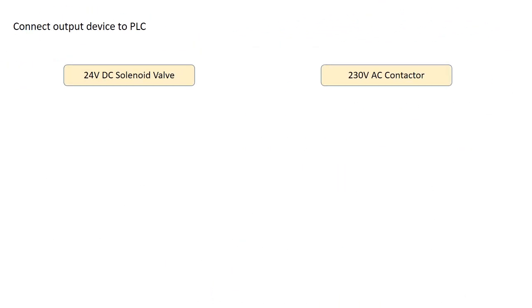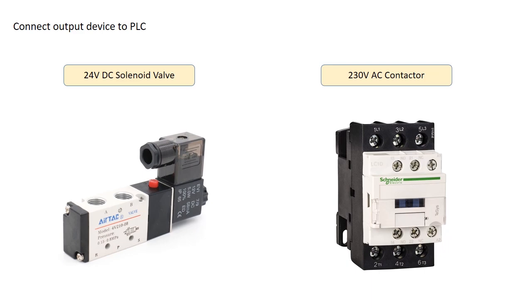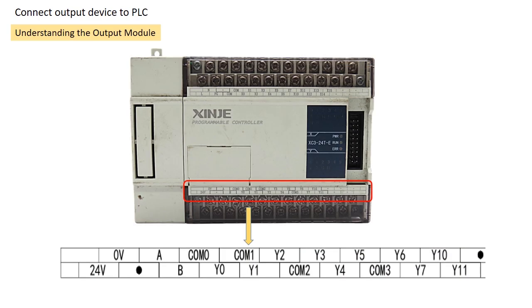Let's see how to set up an output. We'll be wiring two different types of outputs — a 24V DC solenoid valve and a 230V AC contactor — to help you understand the wiring process. Before we start, let's take a look at the PLC output module and identify its terminals. In Xinje PLCs, output terminals are labeled with the Y series, for example Y0, Y1, Y2. In some other PLC brands, you may see outputs labeled with the Q series, like Q1, Q2, and so on.